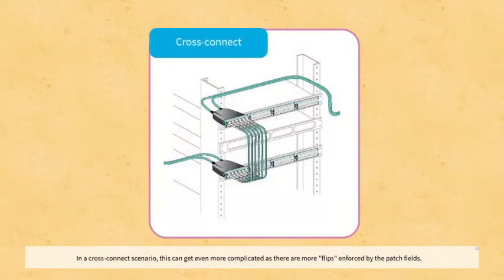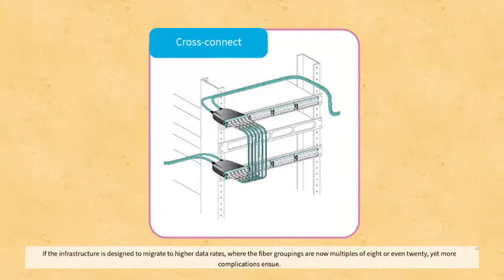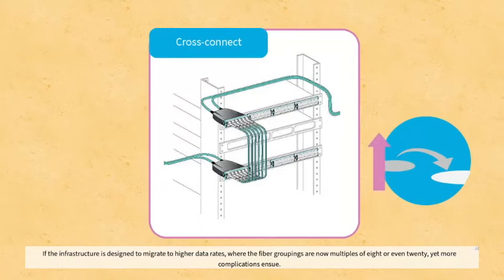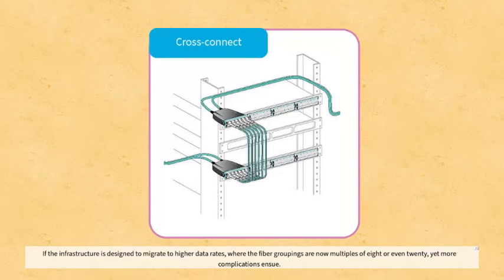In a cross-connect scenario, this can get even more complicated as there are more flips enforced by the patch fields. If the infrastructure is designed to migrate to higher data rates where the fiber groupings are now multiples of 8 or even 20, yet more complications ensue.